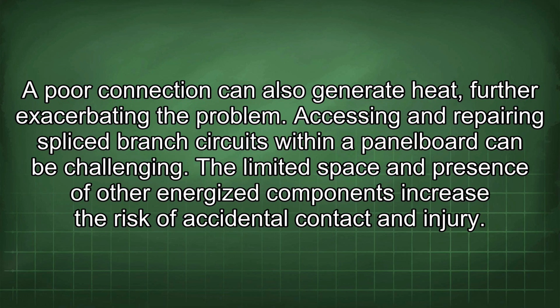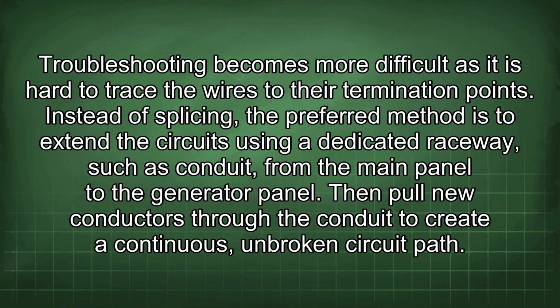Accessing and repairing spliced branch circuits within a panel board can be challenging. The limited space and presence of other energized components increase the risk of accidental contact and injury. Troubleshooting becomes more difficult as it is hard to trace the wires to their termination points.